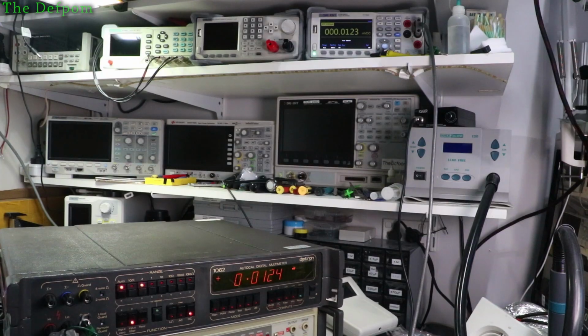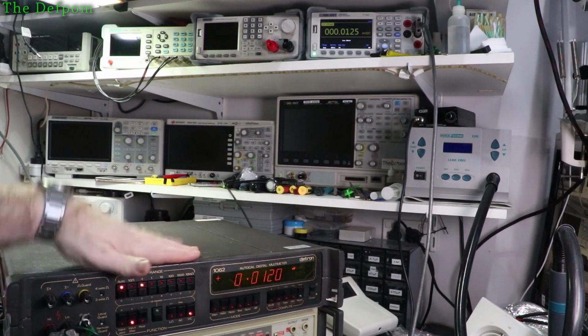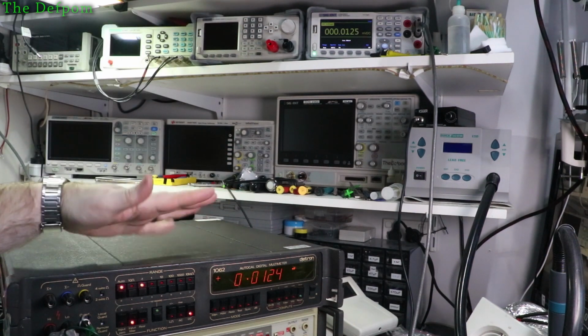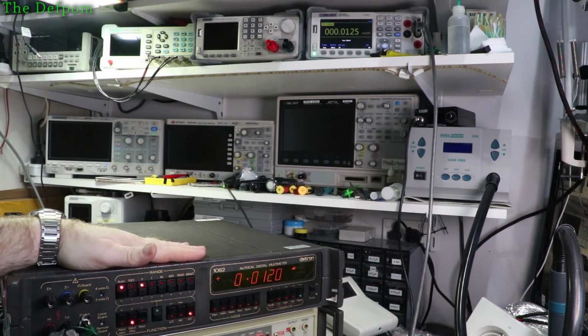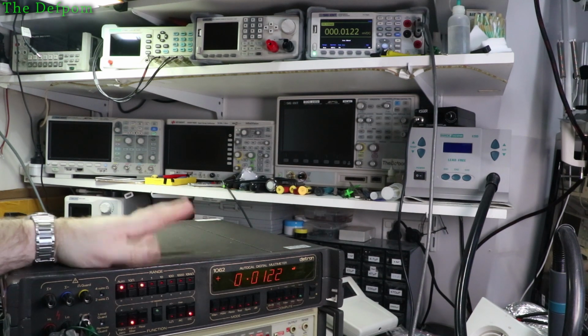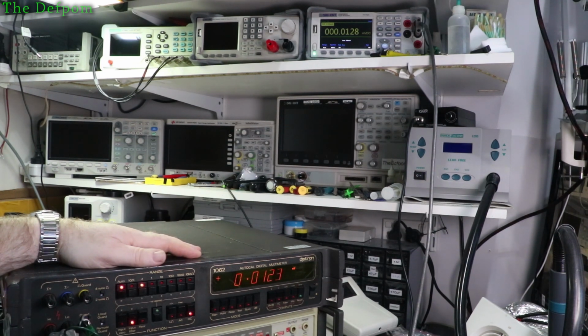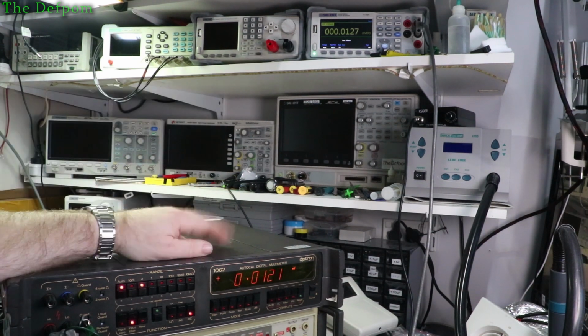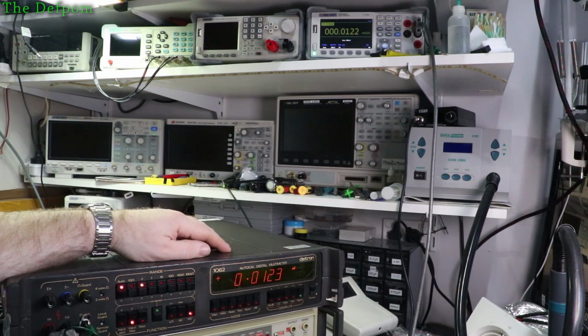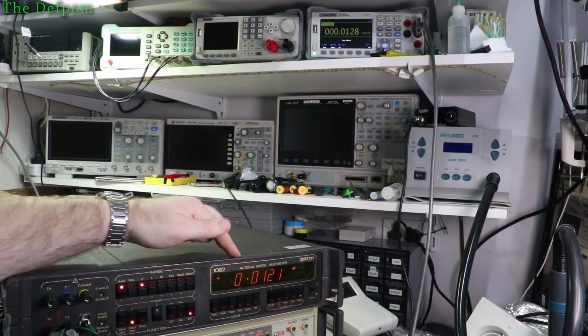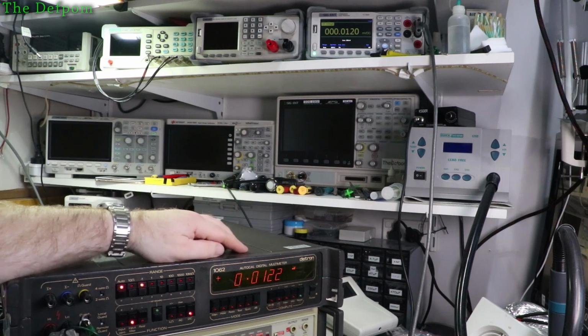Now I've got everything working again. That was a bit of a pain. Oh well. Alright, so I'm just doing a comparison between the Datron after I've done the calibrations and the Siglent up there. So I'm just doing a DC voltage calibration because that's nice and easy, because I can just hook them up in parallel, not have to worry about it. Okay, so my Fluke DC calibrator here seems to have a bit of an offset right now. It's doing 12 microvolts offset. But you can see the resolution, this is comparable.